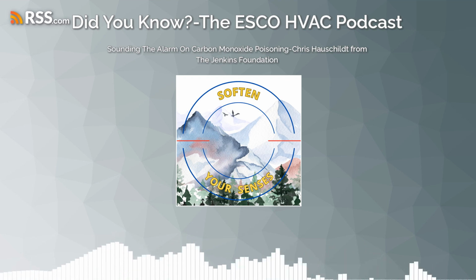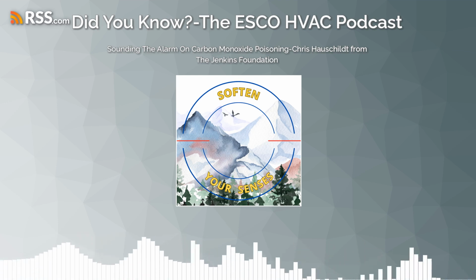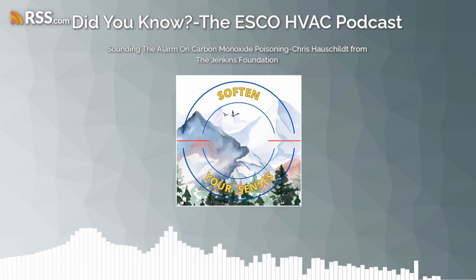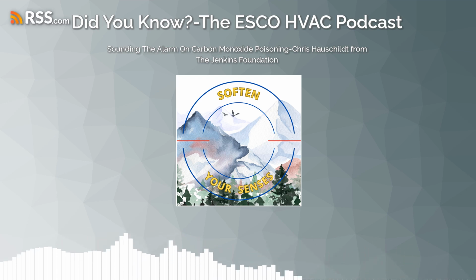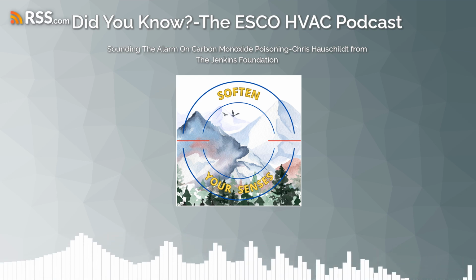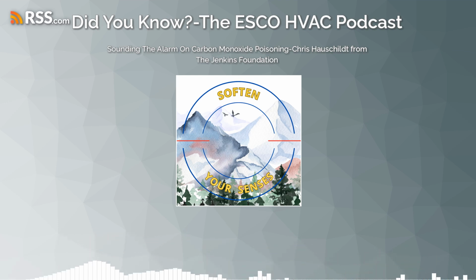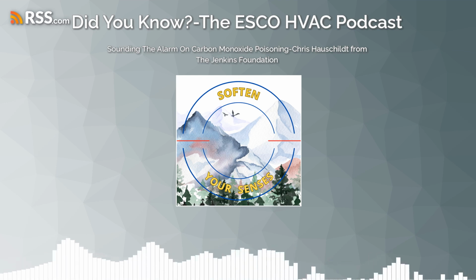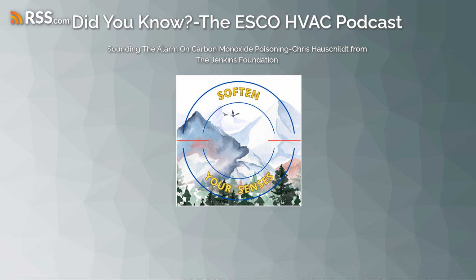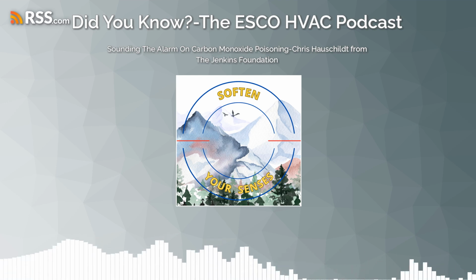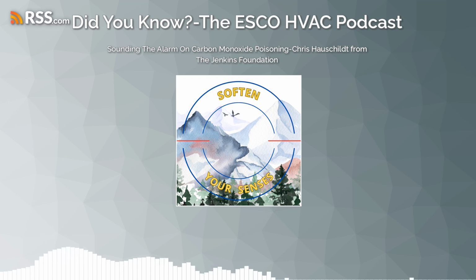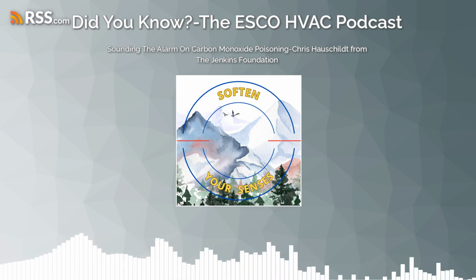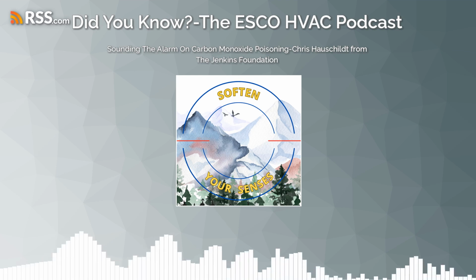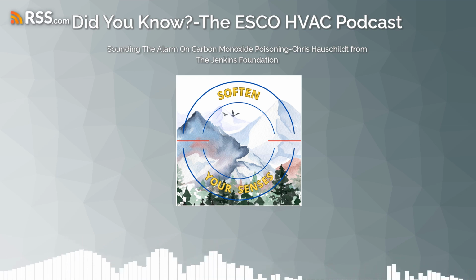Bob, you've spent a lot of time looking at different types of detectors and shed a lot of light on the fact that not all carbon monoxide detectors are built the same. No, they're not. I mean, though there are standards, there are checks and balances in reference to their accuracy. However, unless it's being measured against carbon monoxide, you don't know if it's working or if it's accurate to the degree that is indicated or that a person needs. The due diligence of the HVAC community to enter buildings measuring carbon monoxide with their instruments, that are pre-calibrated, gives a big advantage on a safety issue.